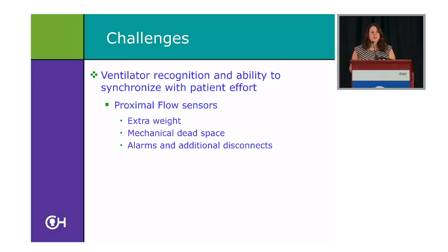A lot of older units have drafts. It's hard when there's a draft in the room and it causes extra humidity in your circuit, which causes problems with your proximal flow sensor. So there are some units that choose not to use them. And there are some ventilator companies that say, you don't need to. We have a proximal flow sensor, but our distal flow sensor works just as well.